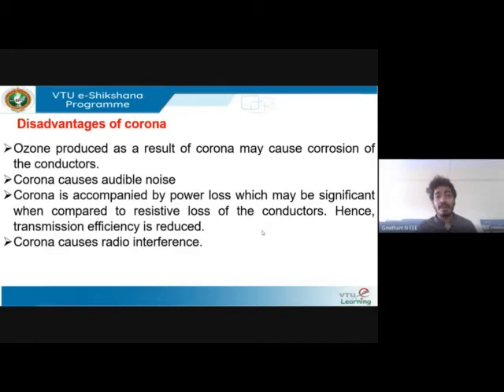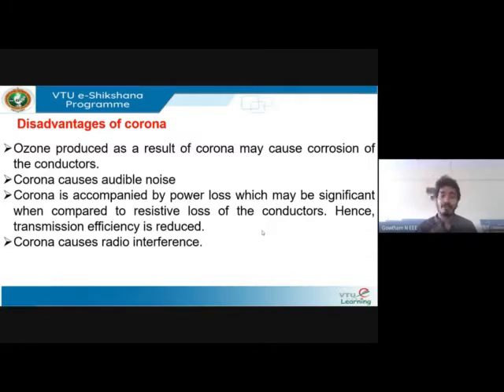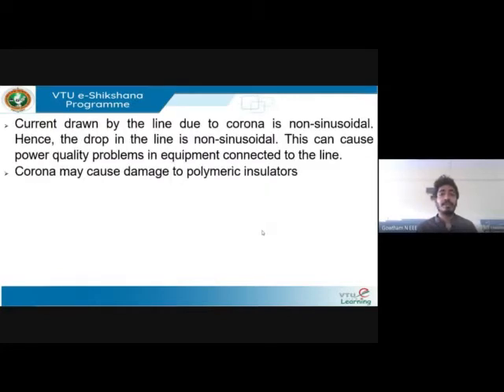Disadvantages: because of the discharge, audible noise is produced. It causes radio interference and power loss. Additionally, the current drawn by the line due to corona may not be sinusoidal, which would cause power quality problems in the equipment connected to the line.